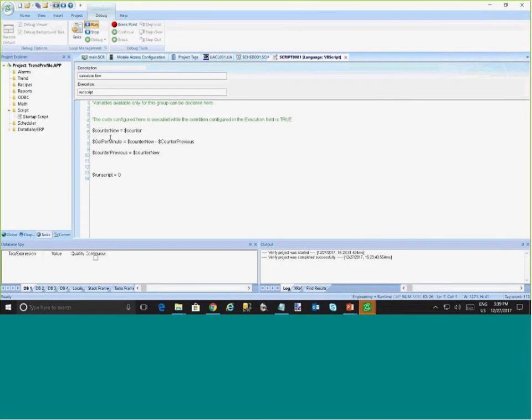So every minute you take the counter to the counter new. The gallon per minute is pretty much one minus the other, usually times a constant. If each counter means, for instance, 50 gallons, then it's times 50. The number of pulses you had in this limit times 50. That's going to be your gallons per minute for that minute. And you write counter new to counter previous, so in the next iteration, you already know the difference. That's at least one way of doing that.